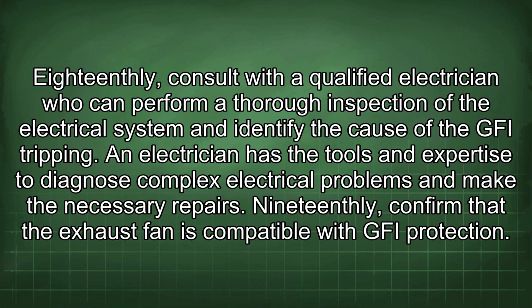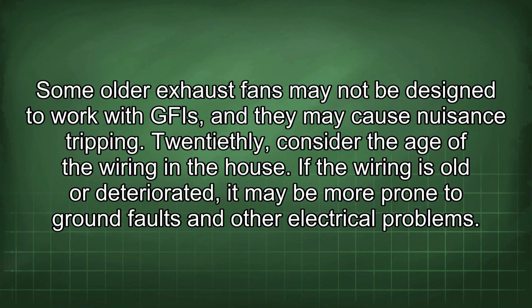18thly, consult with a qualified electrician who can perform a thorough inspection of the electrical system and identify the cause of the GFI tripping. An electrician has the tools and expertise to diagnose complex electrical problems and make the necessary repairs. 19thly, confirm that the exhaust fan is compatible with GFI protection. Some older exhaust fans may not be designed to work with GFI, and they may cause nuisance tripping.